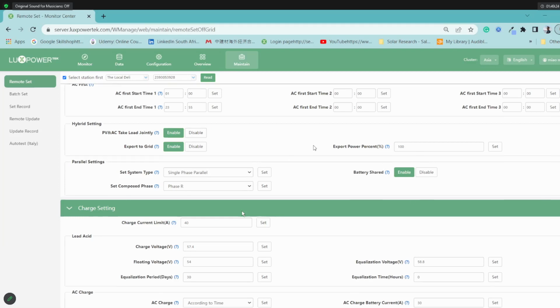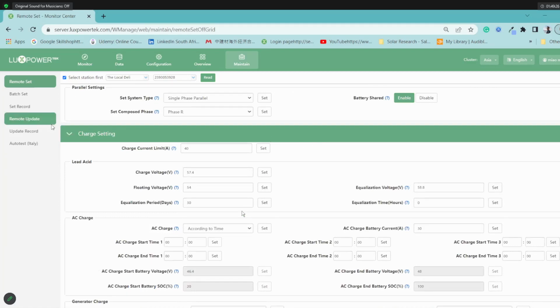Then jumping down to the charge settings, I see in most cases clients leave it at the default of 110. Please don't do that, your batteries are not going to like you for that. So make sure that you know the specs of the batteries.